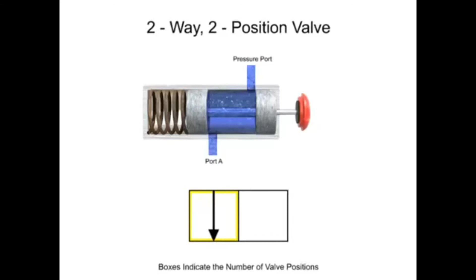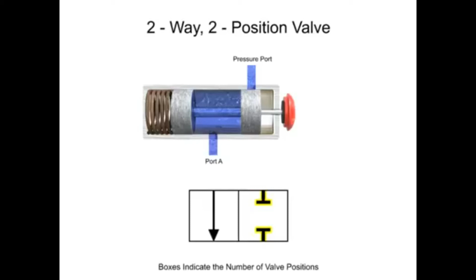A T indicates that a port or way is blocked or closed. This valve's first position has no ports blocked, but its second position blocks both. The second box corresponds to the second position of the valve. Therefore, 2 T's are added to illustrate the lack of fluid flow in the second position. Next, lines are drawn to indicate the normal position of the valve.